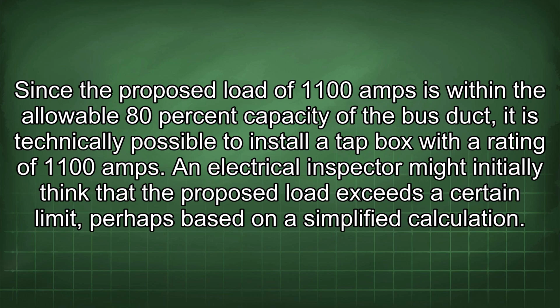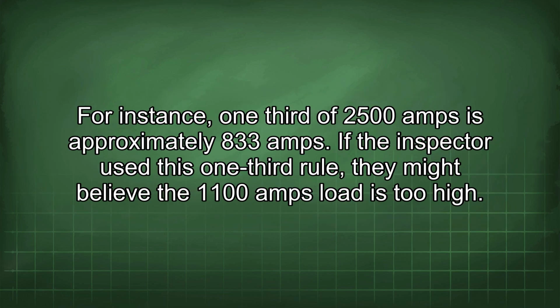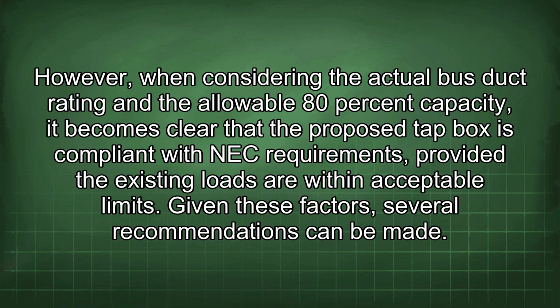Since the proposed load of 1100 amps is within the allowable 80% capacity of the bus duct, it is technically possible to install a tap box with a rating of 1100 amps. An electrical inspector might initially think that the proposed load exceeds a certain limit, perhaps based on a simplified calculation. For instance, 1/3 of 2500 amps is approximately 833 amps. If the inspector used this 1/3 rule, they might believe the 1100 amps load is too high. However, when considering the actual bus duct rating and the allowable 80% capacity, it becomes clearer that the proposed tap box is compliant with NEC requirements, provided the existing loads are within acceptable limits.